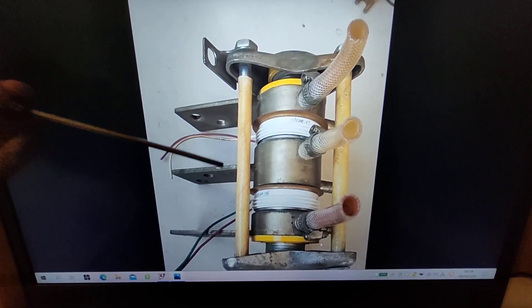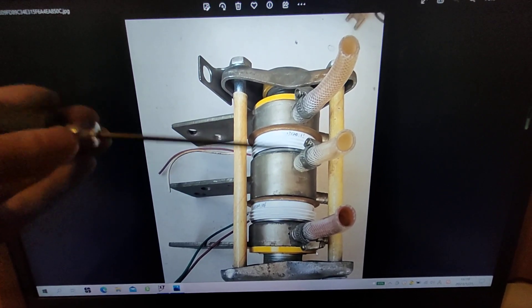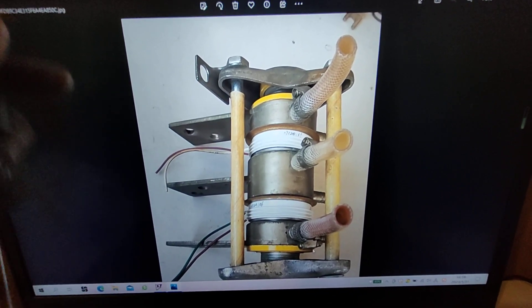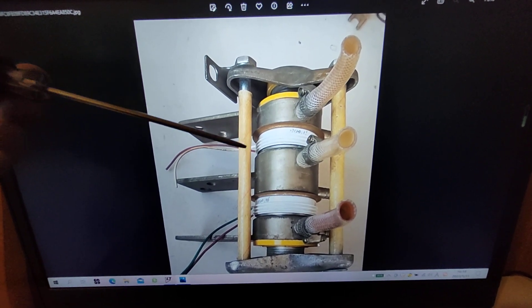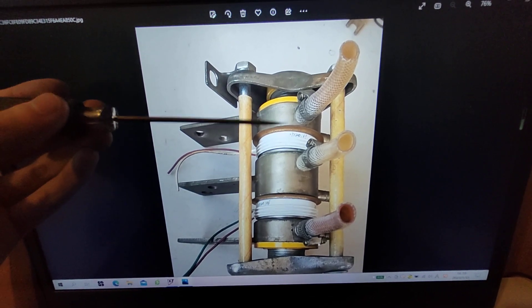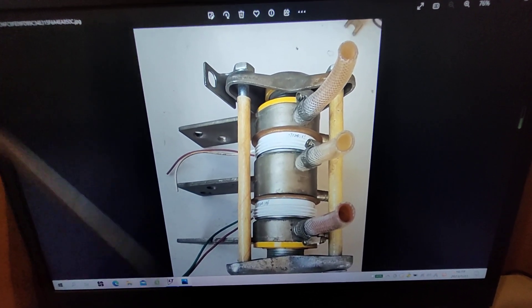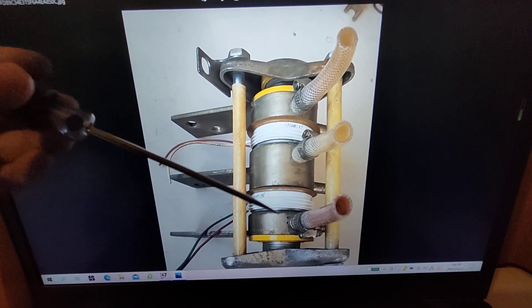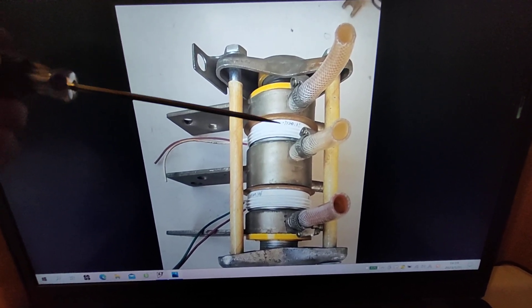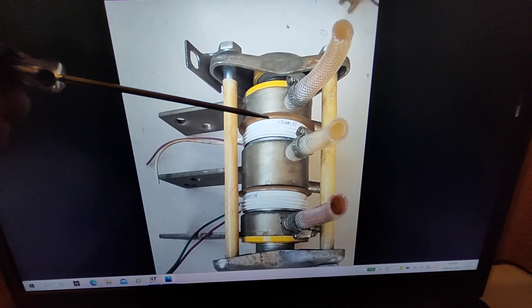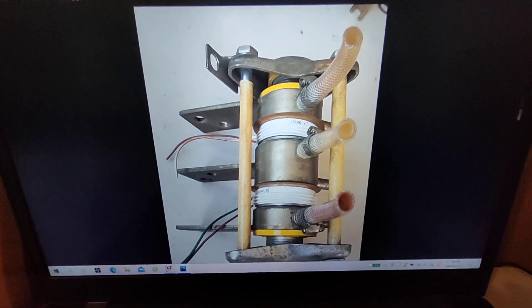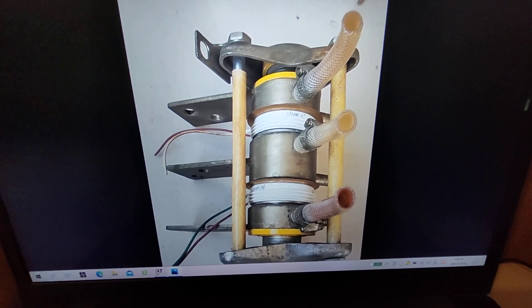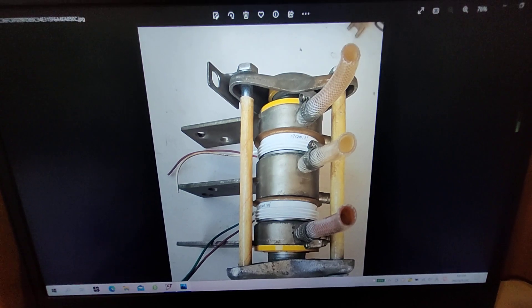Here are three copper bus bars coupling with these two thyristors. And the whole assembly is just pushed tightly by one, two, and three bolts. In the datasheet, it says that these kind of thyristors need to have a mounting force around 40 kilogram force per square centimeter. That's for better electric coupling and to lower the thermal resistance for better cooling.